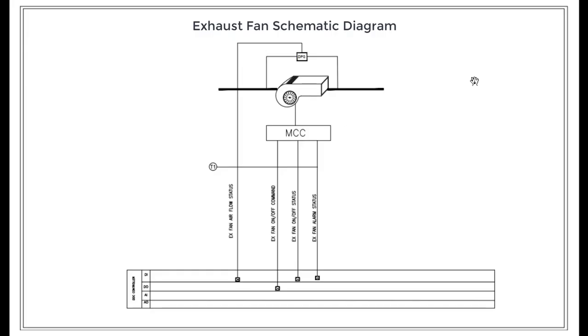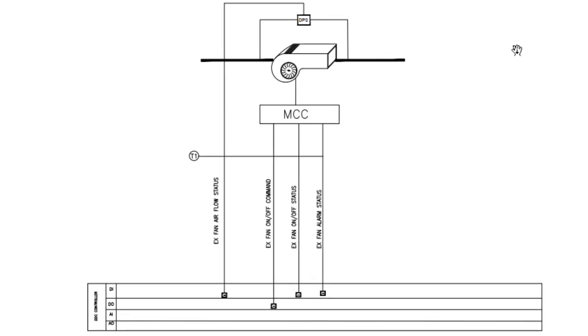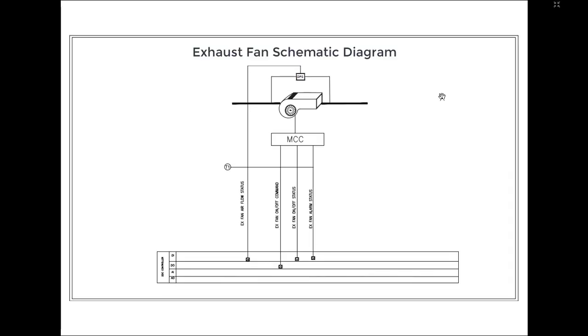Now let's talk about the exhaust fan schematic diagram. Here we have an MCC panel, and we are giving command to the MCC panel and reading the run status and alarm status from the MCC panel. Then we have a DPS switch installed on the exhaust fan to monitor its flow status.